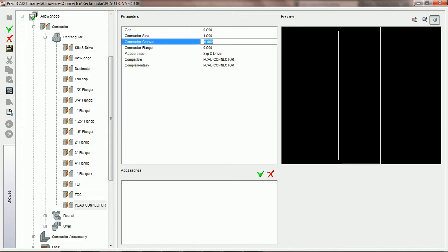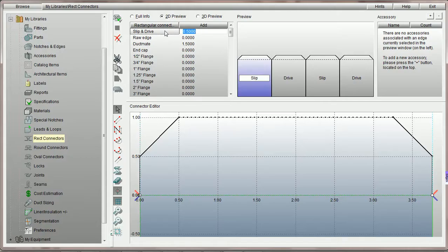To demonstrate that, we're going to show you the connector size parameter inside PractiCAD. Over here in PractiCAD, we are looking at a slip and drive connection. And you could see by taking a look at the way this connection is built that the connection is actually 1 inch long. However, you can see here that we also have another parameter called add, and it is set to be a 1/2 inch. The add parameter is actually in PractiCAD the notch back.